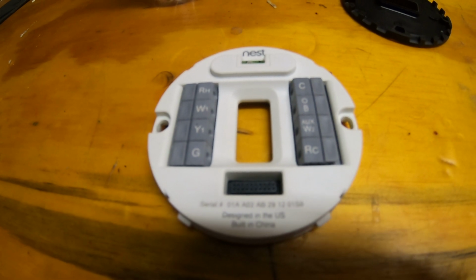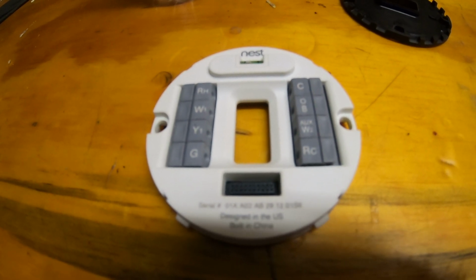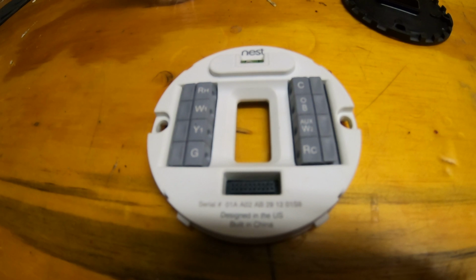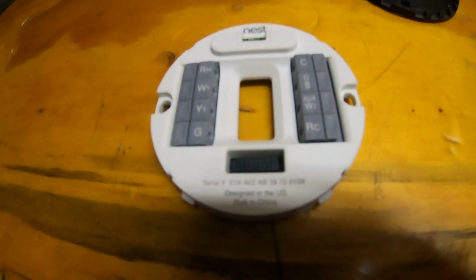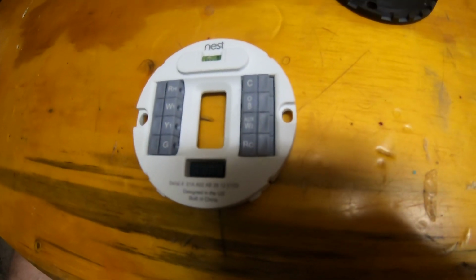The transformer came out to 28 volts AC, which is what you'd expect to see. That was testing between the R and C wires at the thermostat, as you can see on here. So that would be right down here and here. So I saw 28 volts there. I jumped the R to Y, and I saw 28 volts at the contactor, which told me there wasn't a wiring problem.